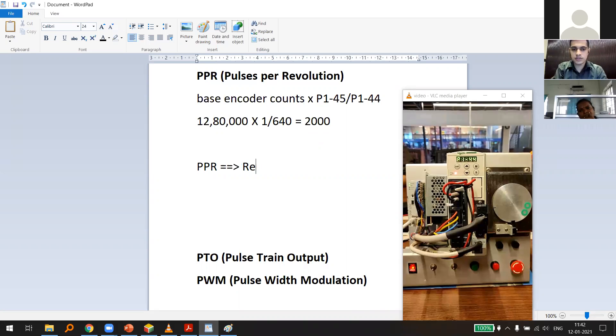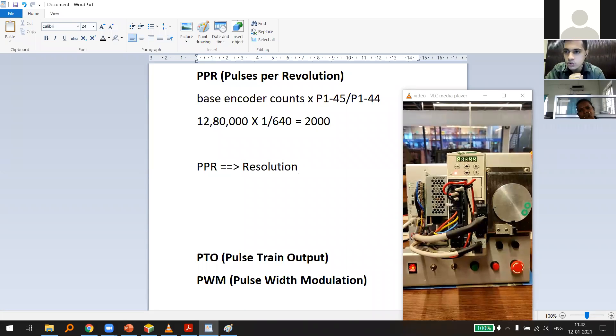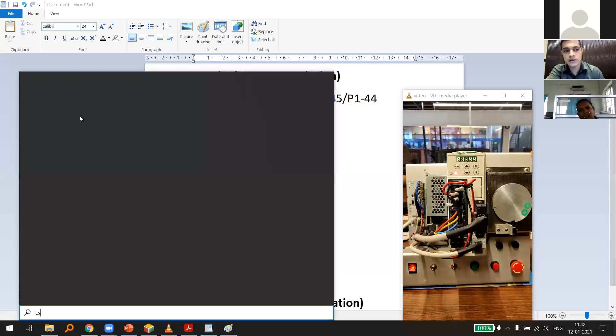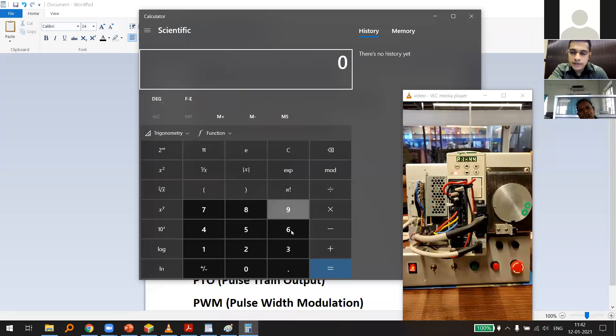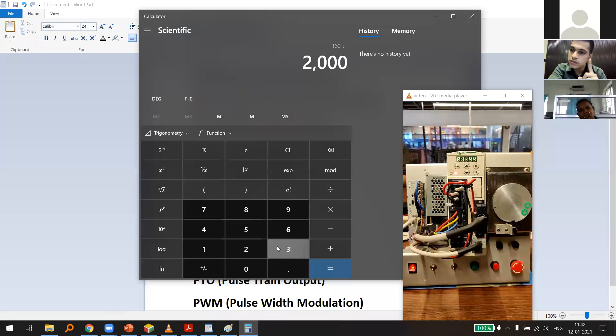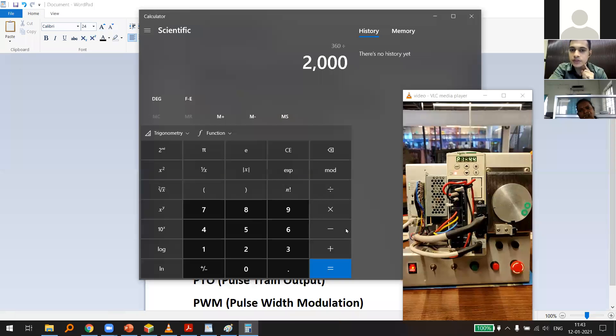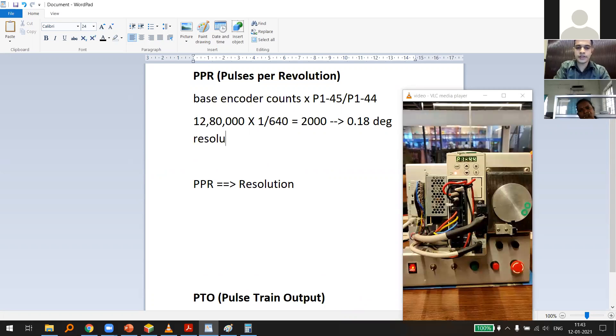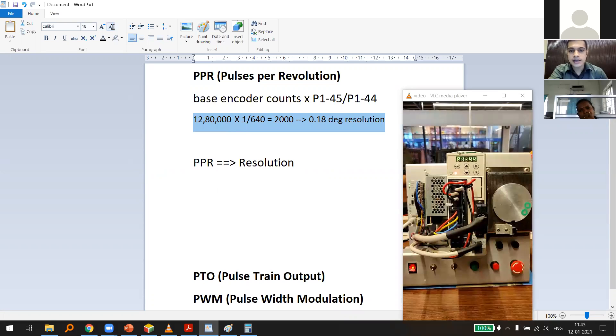Resolution is the smallest unit you can move your servo. With 2,000 PPR, the calculation is 360° ÷ 2,000 = 0.18 degrees per pulse. So with 2,000 PPR, the resolution is 0.18 degrees — meaning you can move the servo shaft with 0.18 degrees of accuracy per pulse.